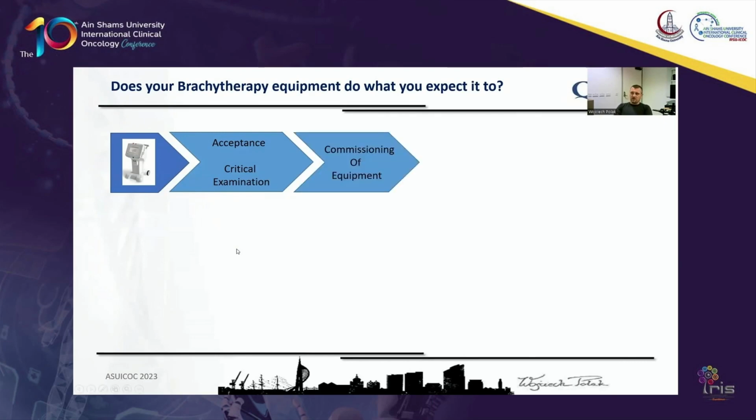Then we've got the commissioning of our equipment. That's the time when we actually do all the measurements, all the baseline that we later use as a baseline for our quality control or quality assurance program. It's a time when we actually learn about our equipment. It's a time that we really have to familiarize ourselves with all of the aspects of the equipment that we just received.